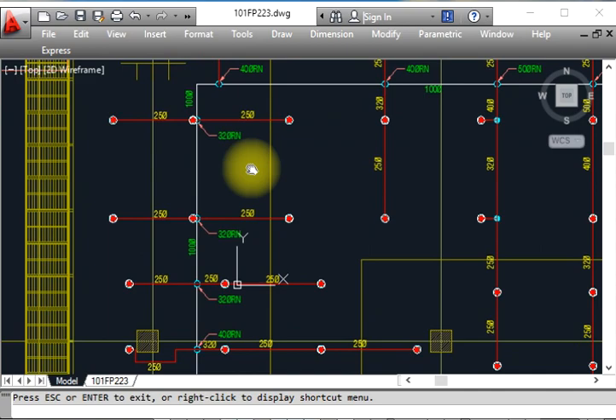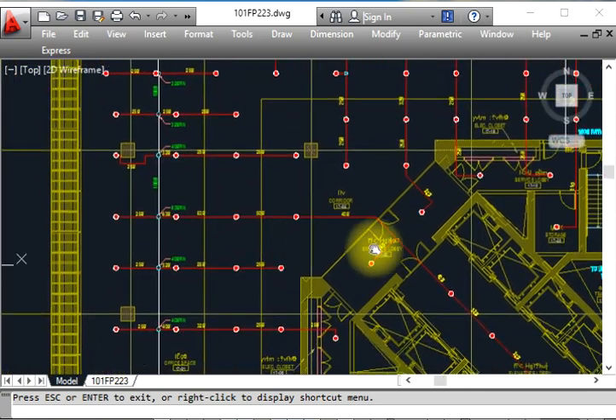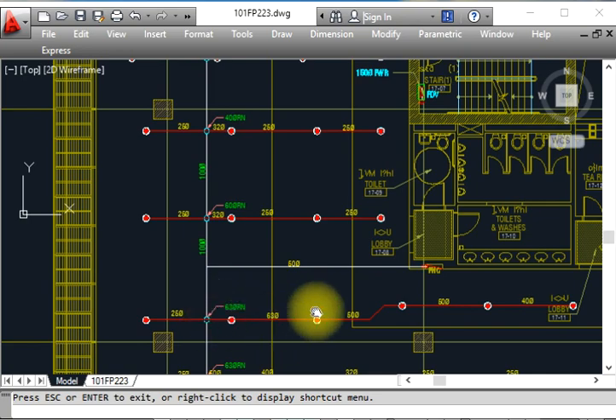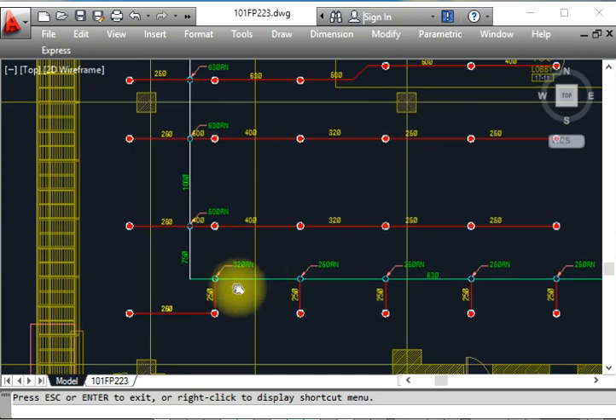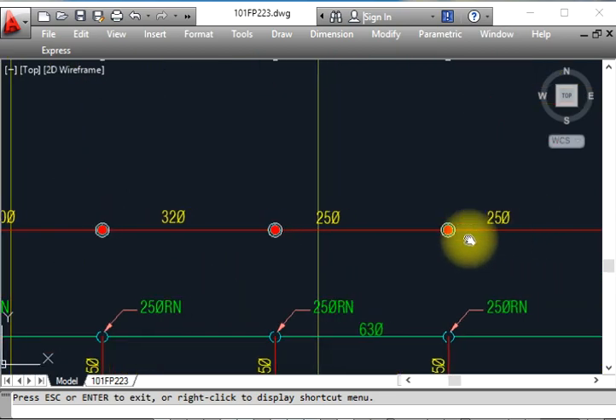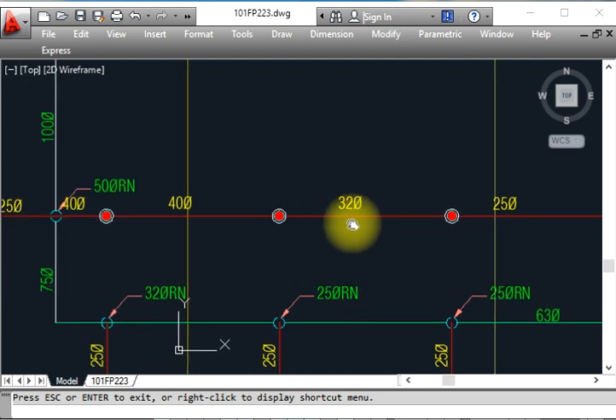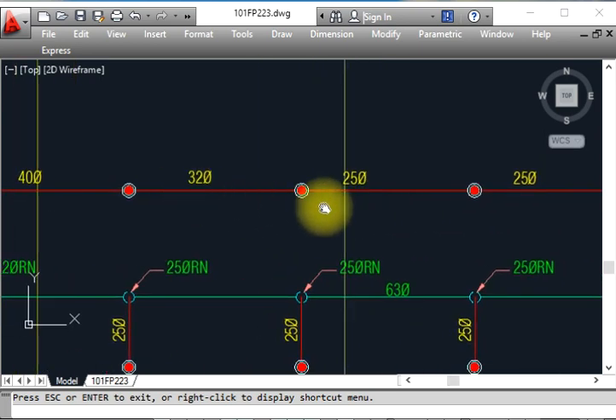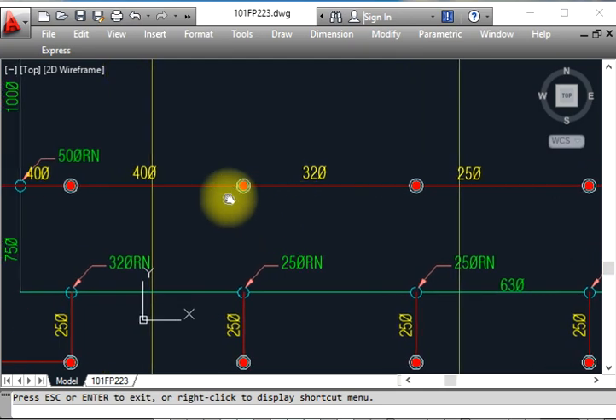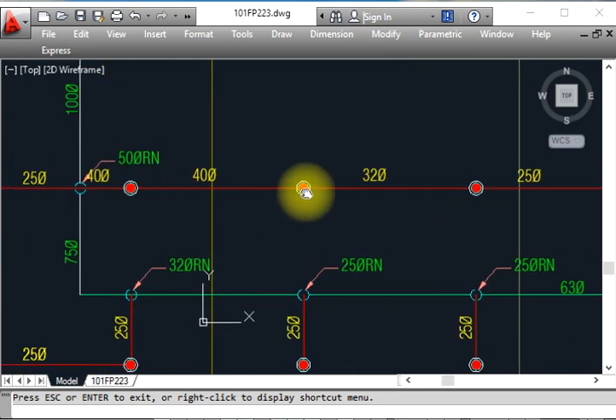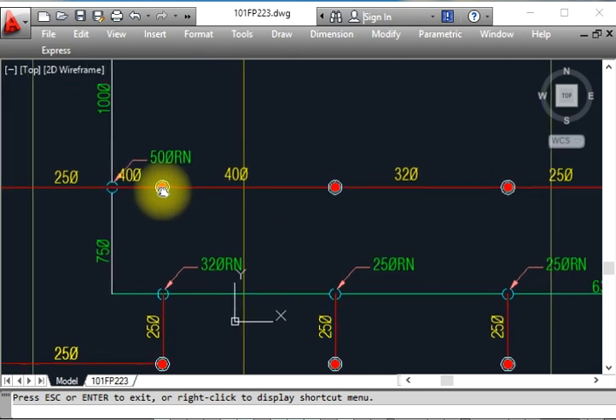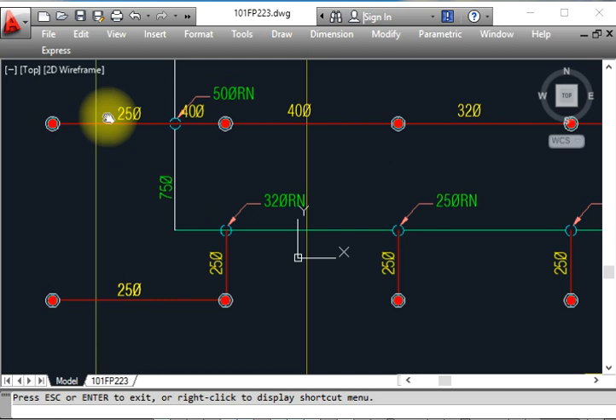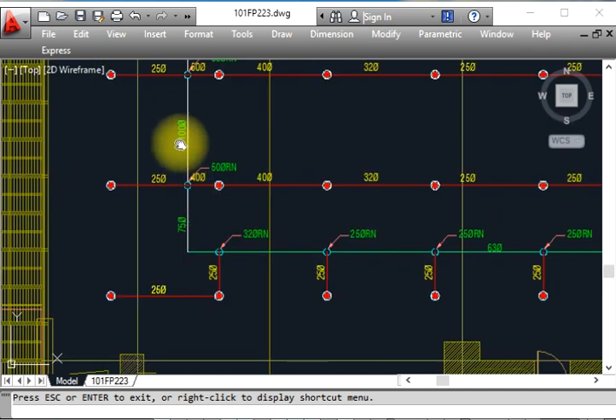I hope you are enjoying and understanding this video. This is the distribution across the left area. The main pipe is going like that — distribution is simple. For example: 25, 25 here, then 25, 25, then 32, 40, 40, and 25 — because two sprinklers are covered at 32mm, 32mm contains one sprinkler, after that 40mm contains two, and after three sprinklers we go to 50mm. So 50mm here, and the riser going up with 100mm, then after 75mm, this diameter.